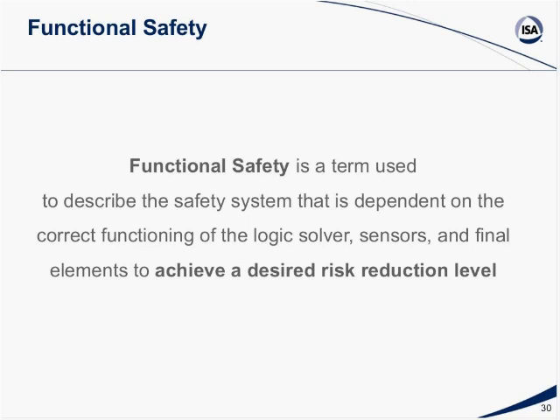So in short, functional safety is a term that's used to describe the safety system that's dependent on the correct functioning of the logic solver, the sensors, and final elements to achieve a desired risk reduction level. Functional safety is achieved when every safety function is successfully carried out and the process risk is reduced to the desired level.